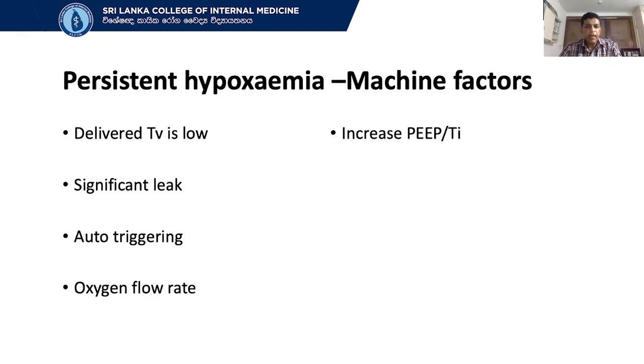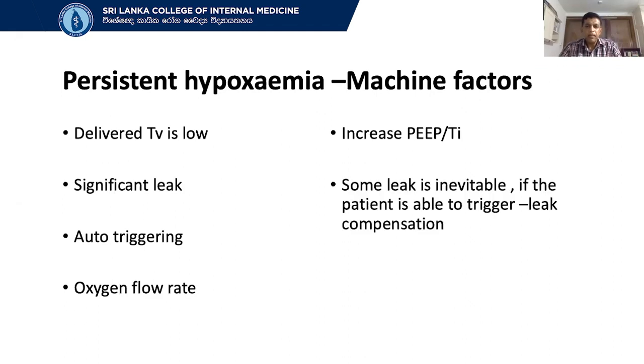And then the main screen usually shows you the amount of leak. Usually there's a leak compensation. 10% of a tidal volume leak is acceptable. Presume that you have a 300 ml tidal volume, then a 30 ml leak is acceptable because the machine compensates for the leak. So what we call leak compensation is always there, but inevitable. Don't try to minimize the leak to zero, because you will end up with a very tight mask and cause nasal or facial ulceration.